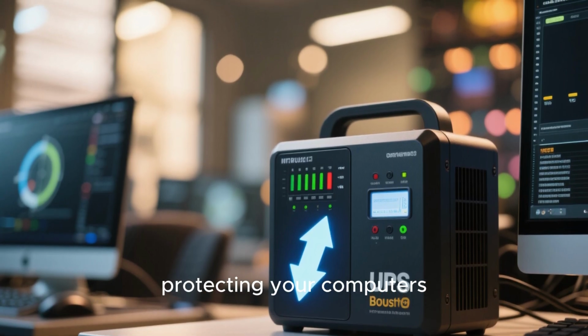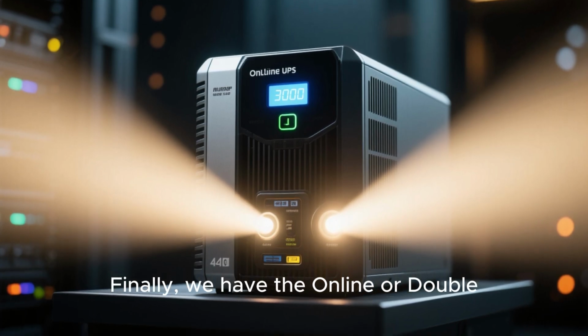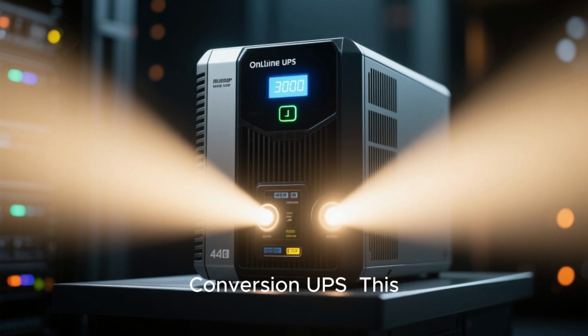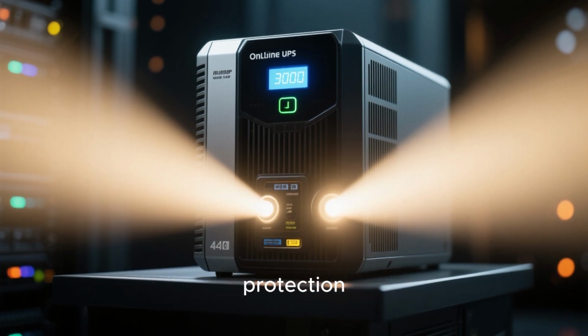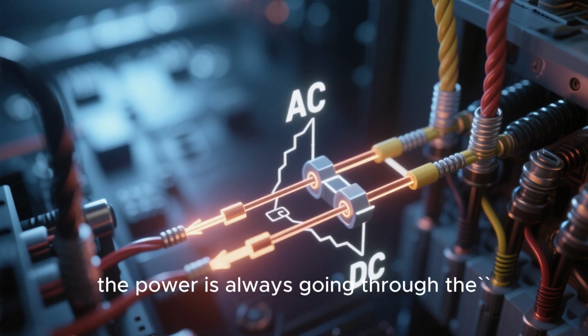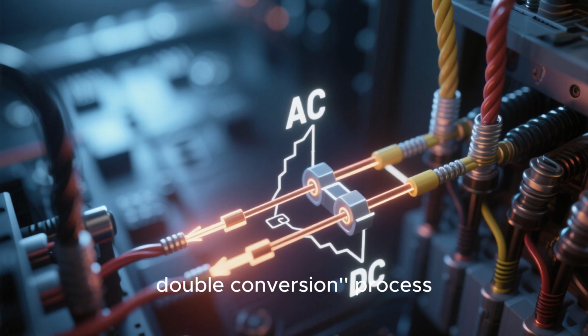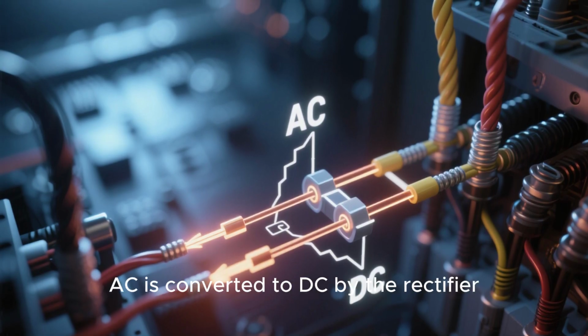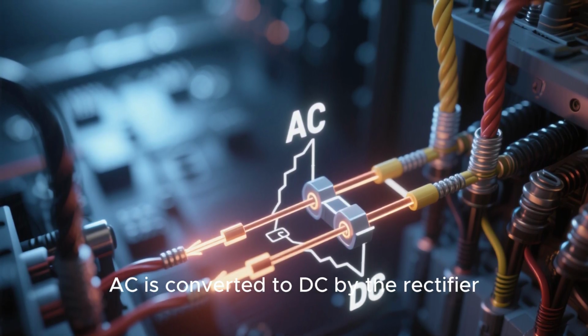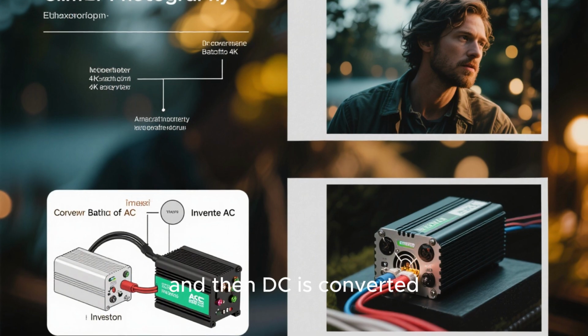Finally, we have the online or double conversion UPS. This is the gold standard of power protection. In this system, the power is always going through the double conversion process. AC is converted to DC by the rectifier, and then DC is converted back to a perfect AC by the inverter.